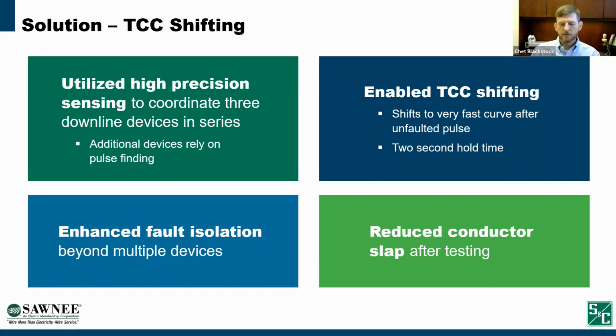So if we have 3 interrupters in series on our system, we coordinate those using traditional methods. But anything beyond that, if we have 4 or more interrupters in series, they still depend on pulse finding to isolate that last segment. So therefore, we had to start using the TCC shifting. So as Mike described, that's where the interrupter shifts to a very fast curve or an instantaneous trip after the pulse detects an unfaulted line.